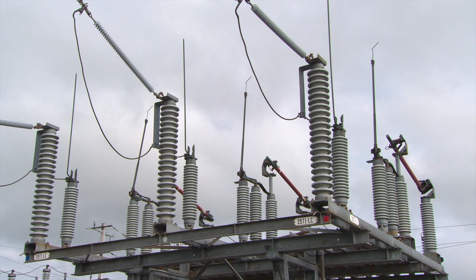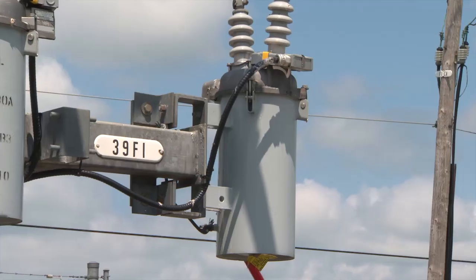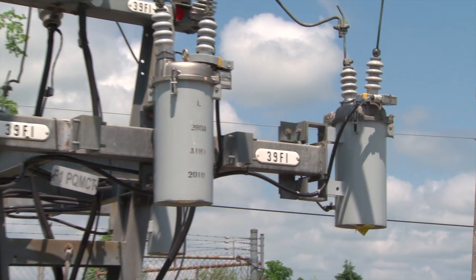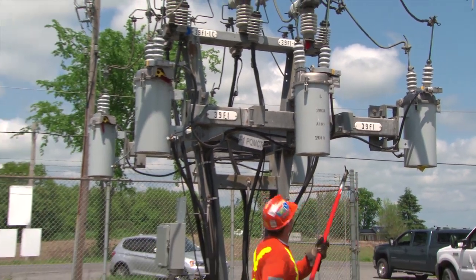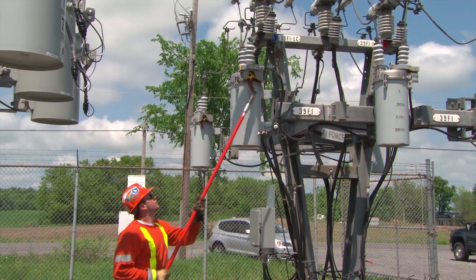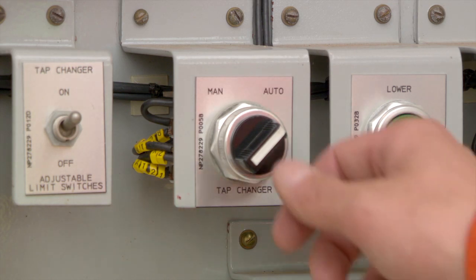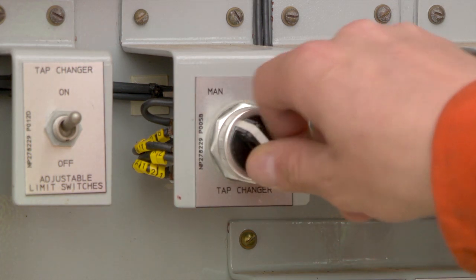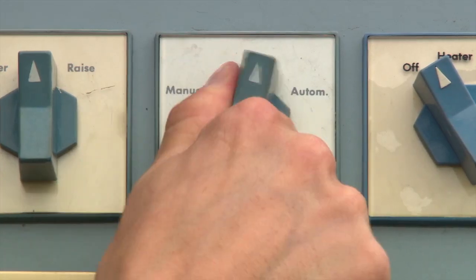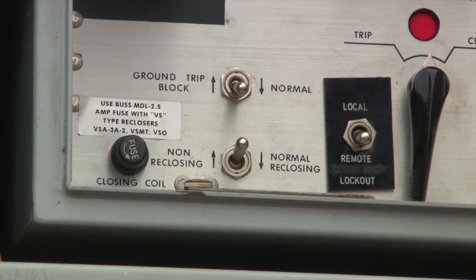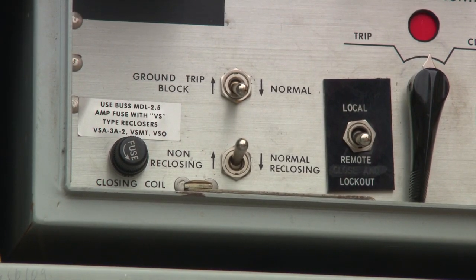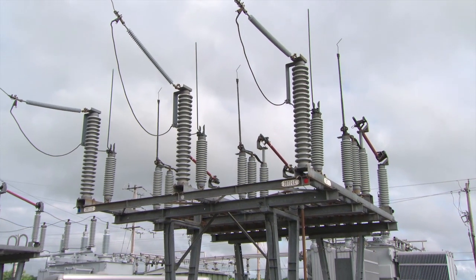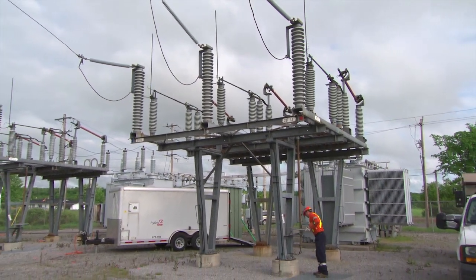Check open the DS high-voltage disconnect switch. Place the DS reclosers in the non-reclosing position. Place the DS and the MUS tap changers in manual. Check that the MUS reclosers are closed and place them in the non-reclosing position. Close the DS high-voltage disconnect switch.